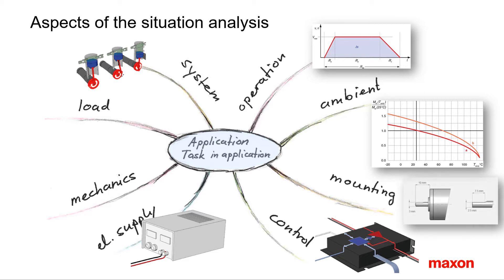Five: mounting conditions, which are also related to ambient — for example, cooling — but also cable length and fixation of the drive. Six: related to mounting is the mechanical layout. What kind of mechanical transformation is used? What are the transformation parameters — for example, reduction, efficiency, friction?